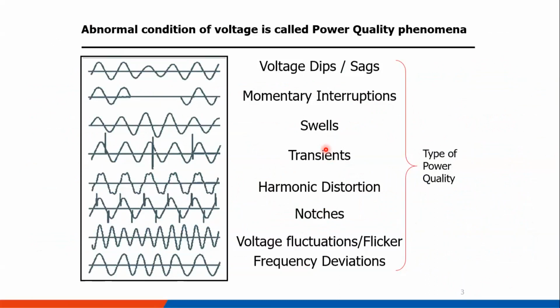So some of the not nice sinusoidal waves are shown here. As you can see here, the first one is the voltage dip or voltage sag. We can see that the sinusoidal has reduced a bit here. This is considered a voltage sag. Momentary interruption. You can see here some of the sinusoidal is somewhat lost. We don't know where it's been. And the swells. Swells meaning the sinusoidal wave has increased a bit. Transient, we can see some spike here. Harmonic distortion, as explained by the previous speaker, a bit jagged. The sinusoidal is a bit jagged, and not just having some spike, repetitive spikes. Voltage fluctuation or flicker, having uncertainty of voltage variations, and the frequency deviations, the frequency adjusts itself.